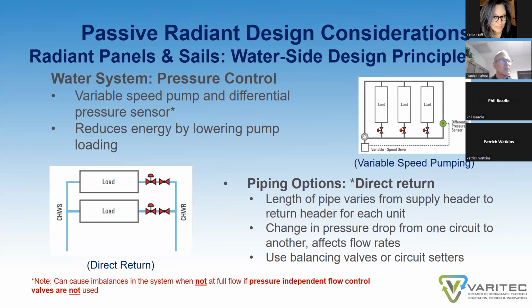Some design considerations on the water side. Make sure that the chill water system and hot water system have a variable speed pump design, so you're maintaining the proper fluid flow rates throughout the building at all points. You can use a variable speed pump to do that, to maintain the actual water side pressures necessary to get adequate flow to each of the devices in each of the zones.